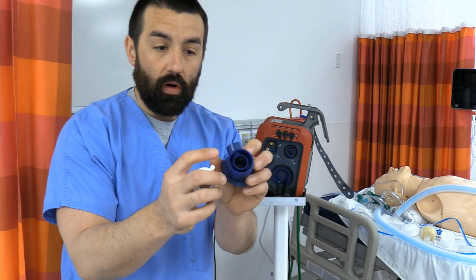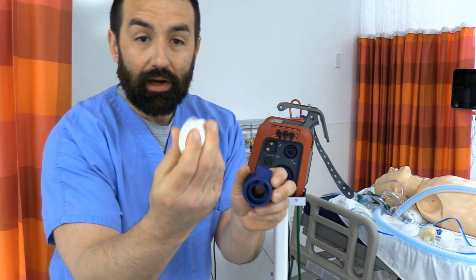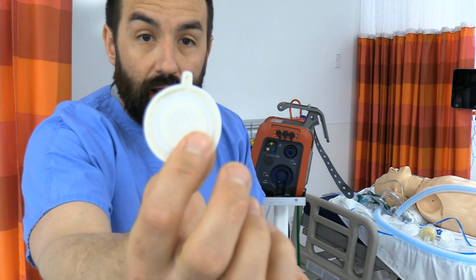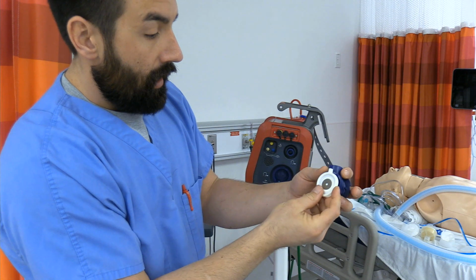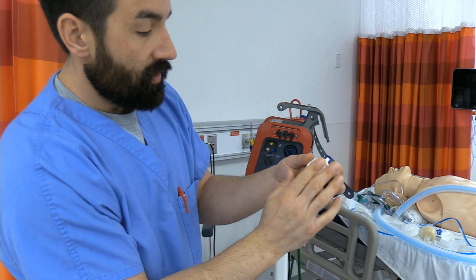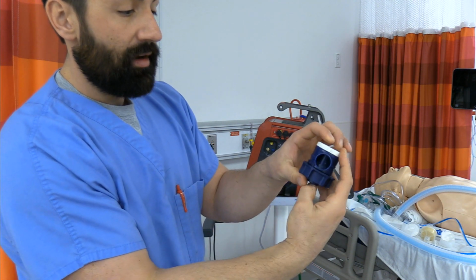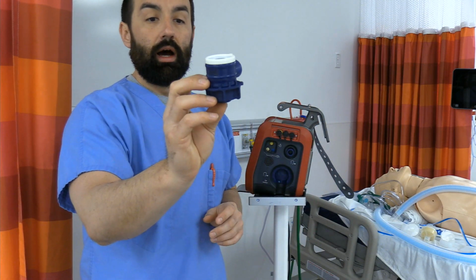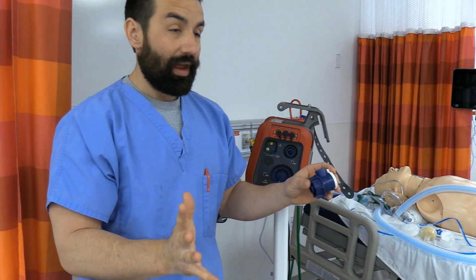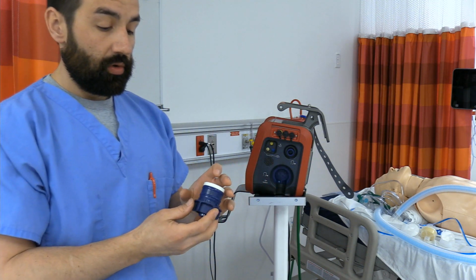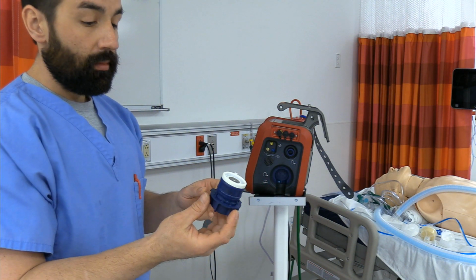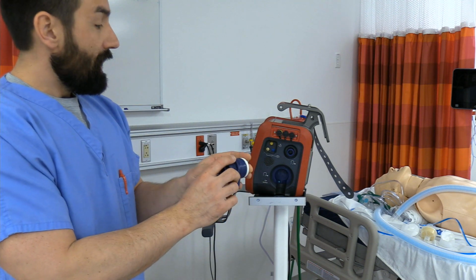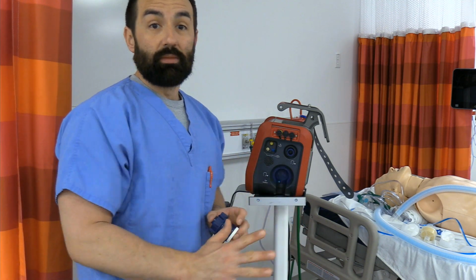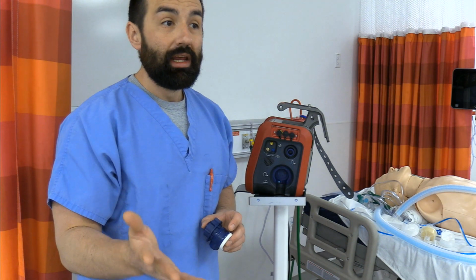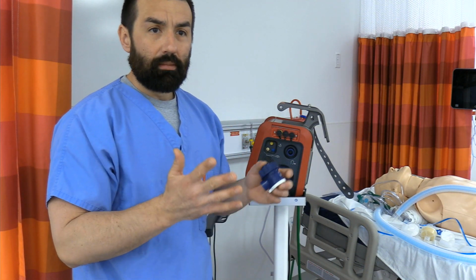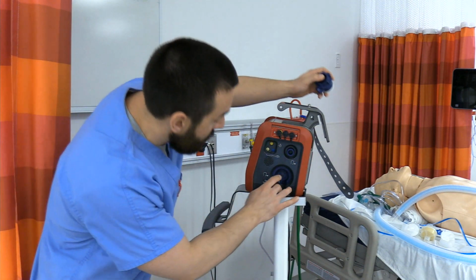and on the T1, we have this little notch right here. It needs to correspond with that little notch, all right? And we're going to seat this on. So once that diaphragm is installed, this is the whole exhalation mechanism for the Hamilton. Once again, this is a reusable, and I'll show you a disposable one in a moment. This enables the ventilator to seal the system when we're trying to deliver gas to the patient. It also allows us to maintain precise levels of PEEP and things like that.